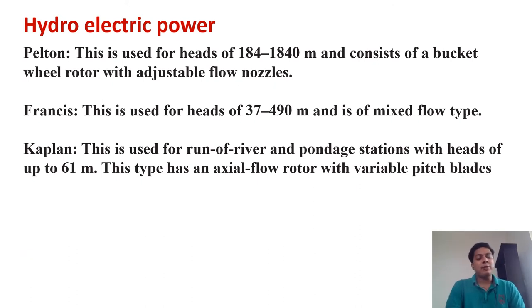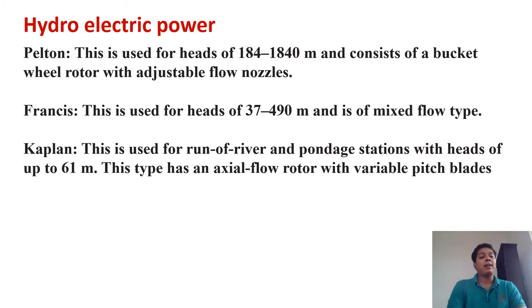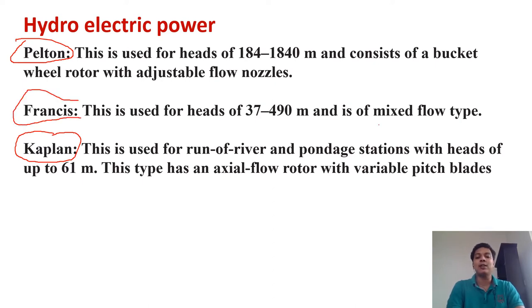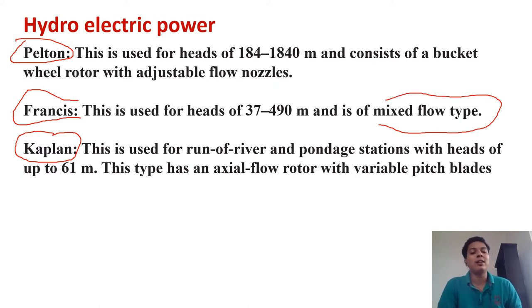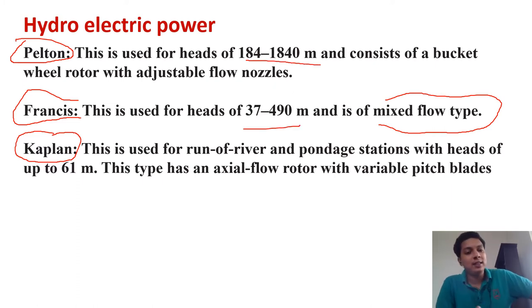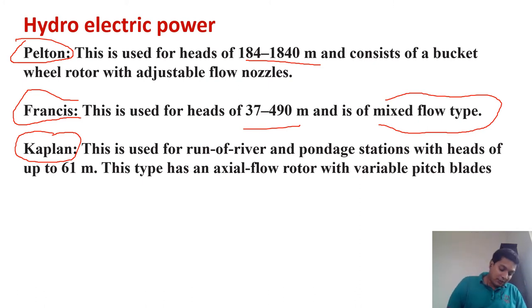We use different types of turbines: the Pelton turbine for high head, the Kaplan turbine for low head, and the Francis turbine for medium head — which is why Francis is called a mixed flow type turbine. Idukki power plant uses the Pelton type turbine because of its high head conditions.